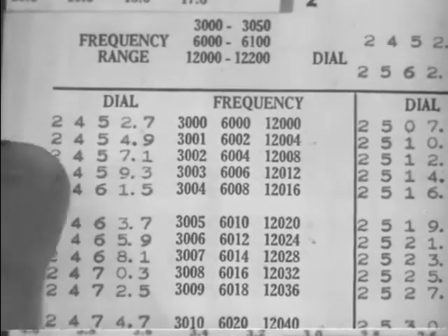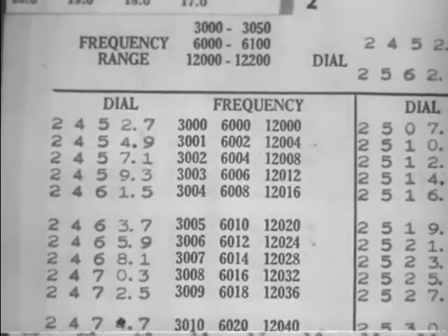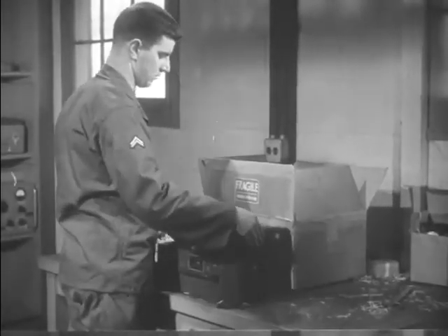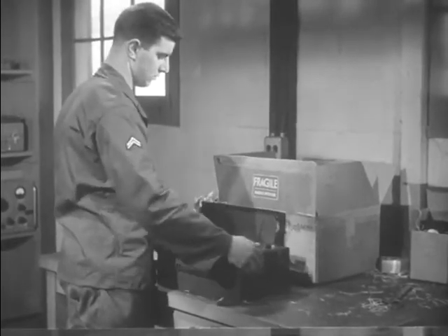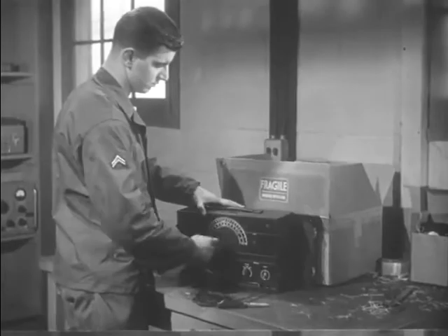A tolerance of 1 or 2% is allowable on most signal generators. Of course, this procedure must be accomplished on each band to check the accuracy of the entire range. Remember, these are fine precision instruments. Dropped or mishandled, their immediate value is at an end.